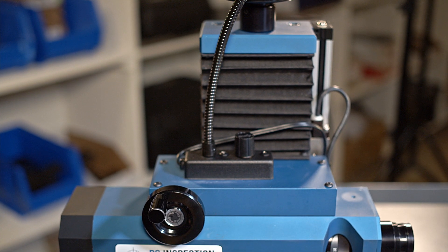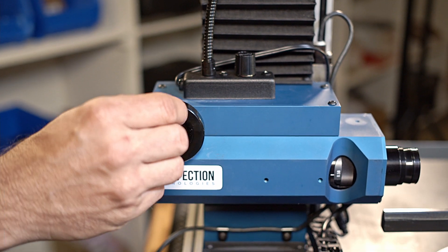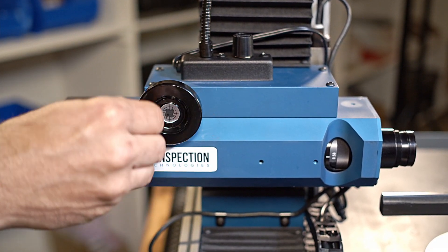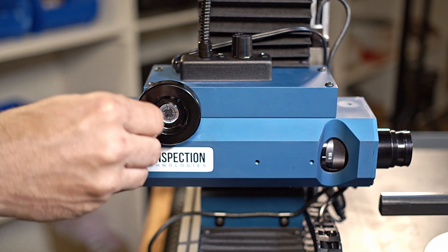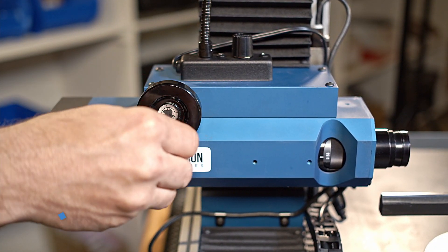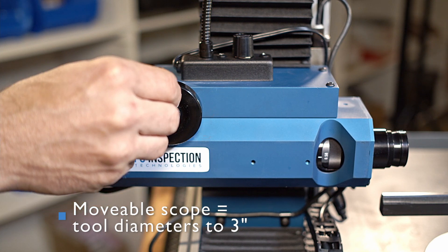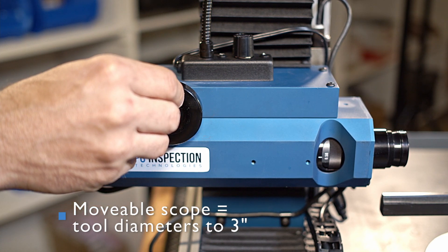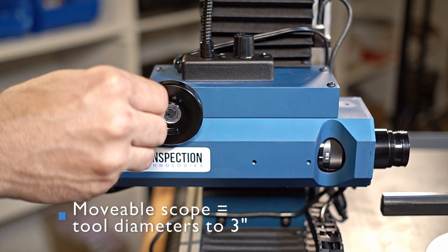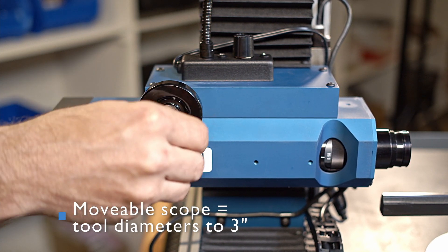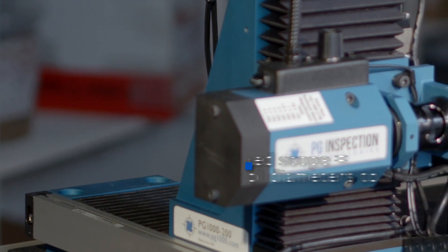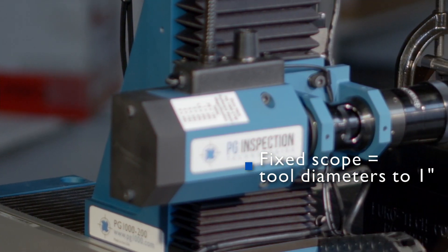The microscope assembly on the 400 is engineered to travel backward and forward. This movement allows for a wider range of focal lengths, which makes it possible to inspect a larger diameter tool than would be possible with the fixed focal length of the 200.